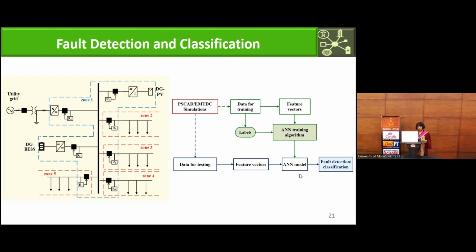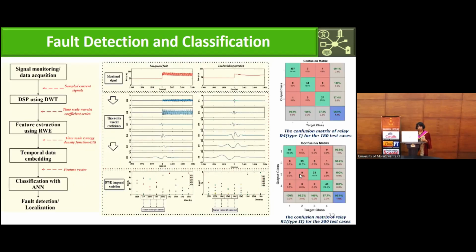We trained a neural network to detect and classify the faults, and we developed two types of relays, one with primary protection only and the other with primary and backup protection. This shows the process of detection, one for fault situation and another for a load switching situation, both giving transients, and the results processing is shown here. We were able to get very high accuracy for both types of relays - nearly 99% accuracy was achieved. These studies were done with a huge number of data.